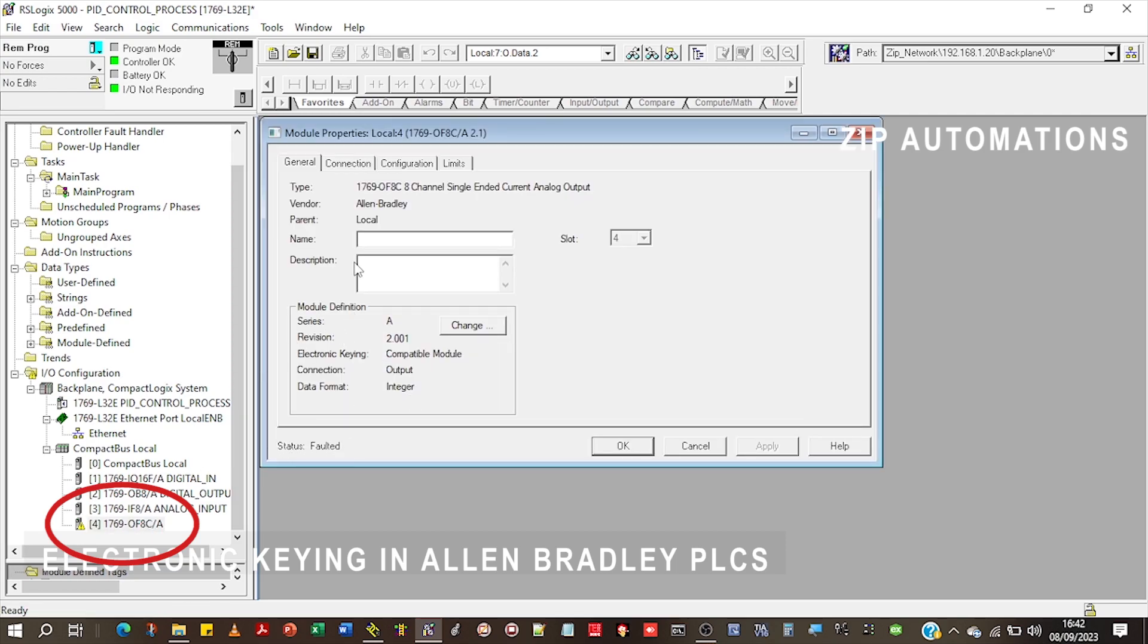Anytime this happens, the first thing that you need to check is whether the module is actually connected online and check whether the revision you have in your project matches the actual revision on the card.